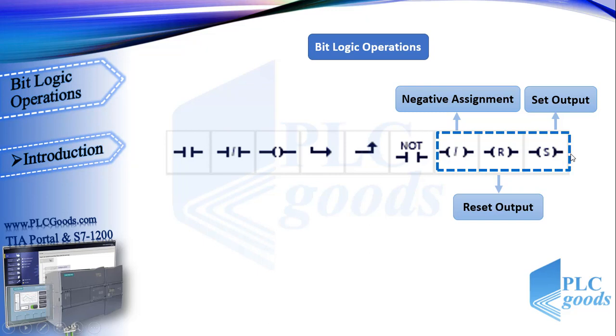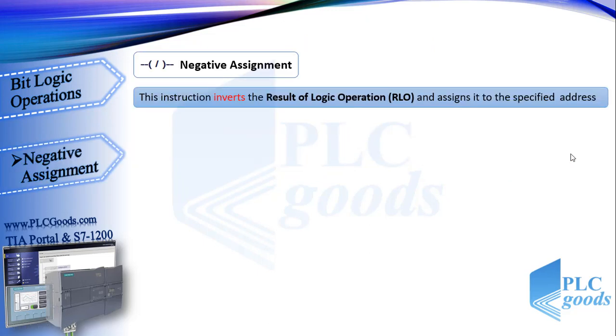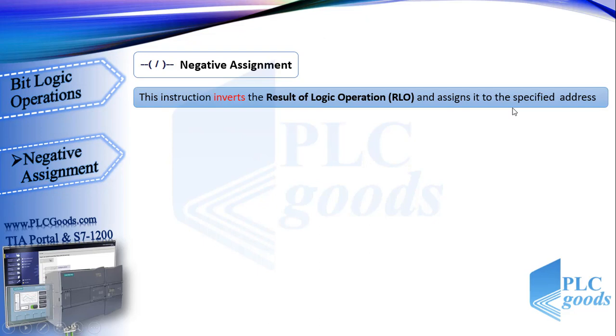Now we're going to see what are these instructions which are similar to assignment. First, let's see negative assignment. This is the ladder symbol of negative assignment instruction. This instruction inverts the result of logic operation RLO and assigns it to the specified address. If you remember, in ladder language, RLO is the same as virtual power.